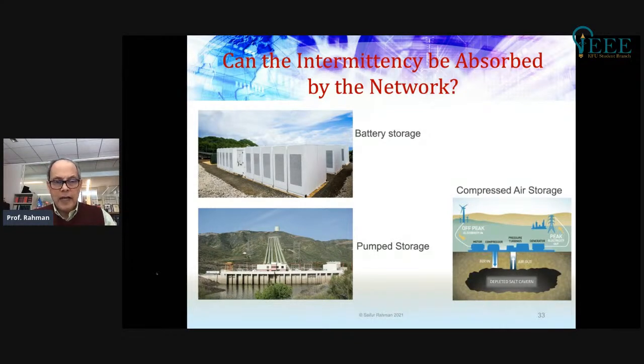On the right-hand side, I have a different technology called compressed air energy storage, CAES. How does it work, and why do you need it? Any gas turbine, very common in Saudi Arabia, has to compress air for combustion, which requires electricity to run the motor. If you're running these gas turbines during the afternoon high demand period, you're pulling more power from the system to compress the air first and then run the turbine. That's expensive. What we're showing here is this technology for compressed air energy storage.